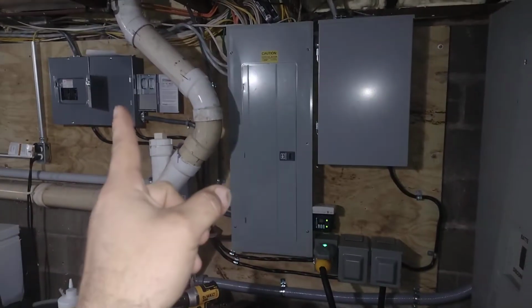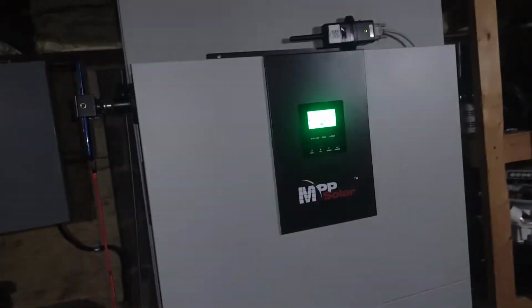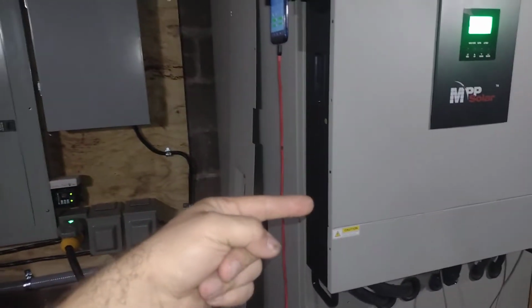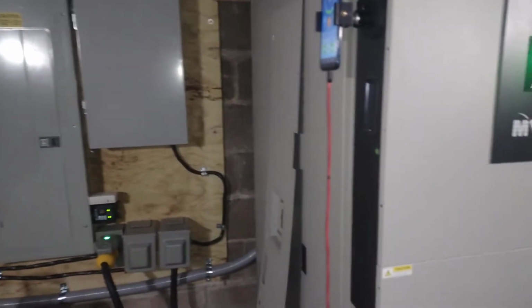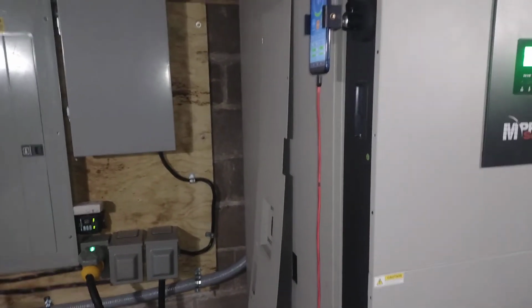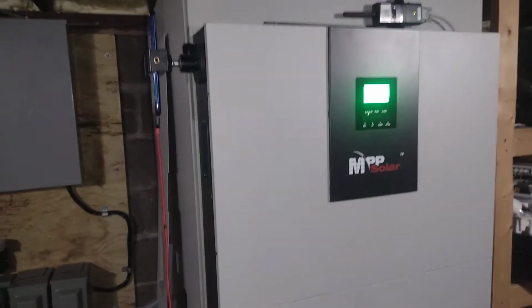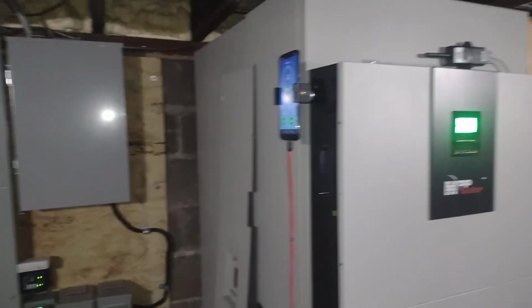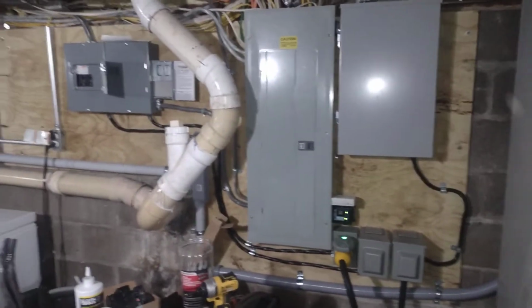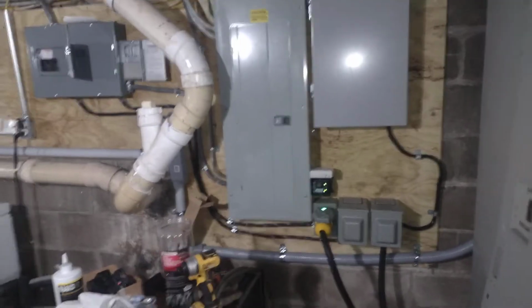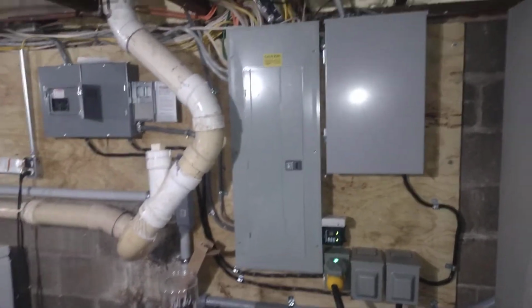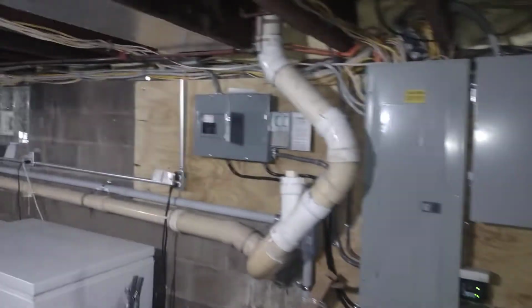Well, then why not just flip that switch and just run the generator right into the house? The point is, I can come in here and change a setting and then charge my batteries while running the house. And this way, when the batteries are charged, I can shut that generator off. That's not super fuel efficient. It's a big 12 kilowatt military generator. And then I can run for another day or 3 days once I get the other batteries hooked up on just batteries, right? So the generator would only have to be on when it's loaded, which is also good, prevents wet stacking on that diesel generator. So that's what all that is.